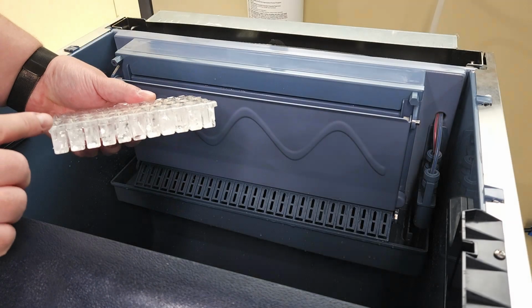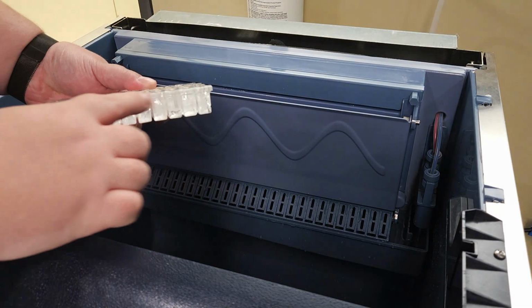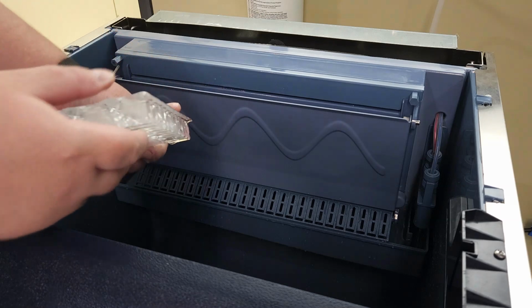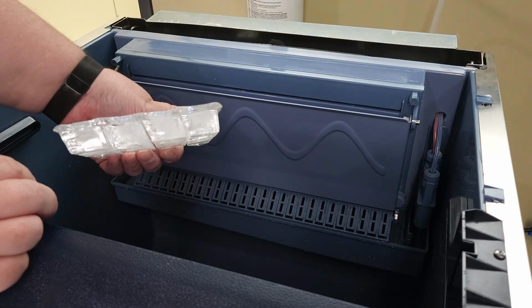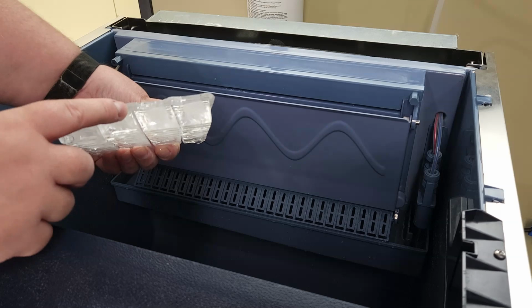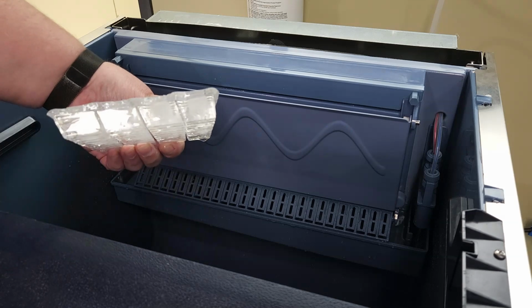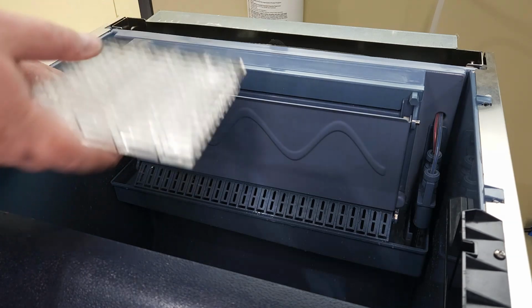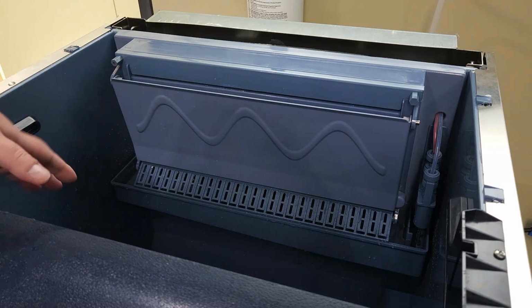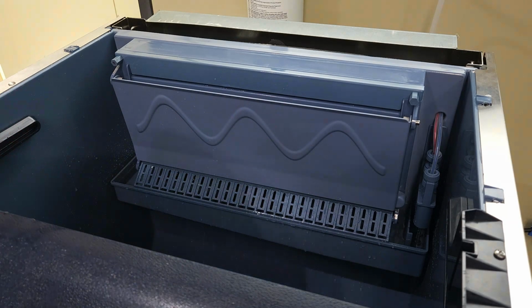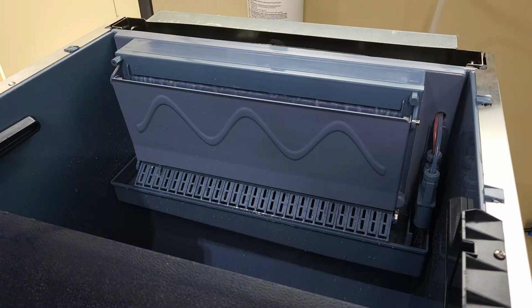Wait for the ice maker to drop a batch of ice. Then pick up the ice out of the bin and look at the width of the ice between the cubes. This is called bridge thickness. You are looking for around 1/8 of an inch in thickness. This will ensure that when the ice drops, the cubes break apart easily. This batch is closer to 1/4 inch in bridge thickness, so we will need to adjust our harvest probe up to thin out the ice bridge.